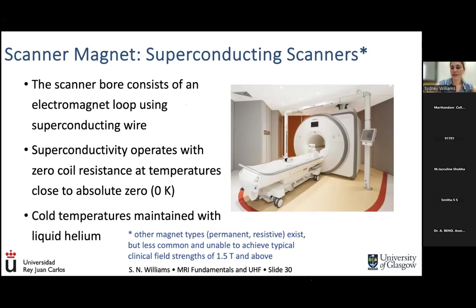Although there is a caveat, because there are other types of MRI scanners available that use either a permanent magnet or a resistive magnet, which is the classic type of electromagnet I was talking about. But those types of MRI scanners are not as common, and they cannot get to the more usual clinical field strength of 1.5 Tesla or above. So you'll see those for specialty applications. For example, a lot of orthopedic imaging can make use of other types of MRI scanners with different magnet types.